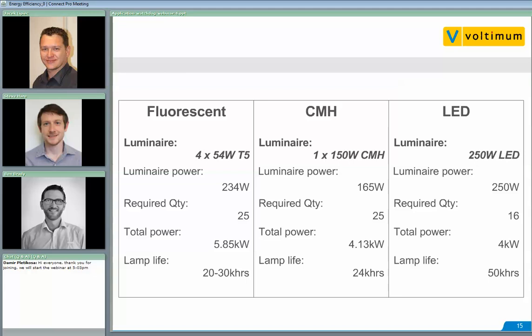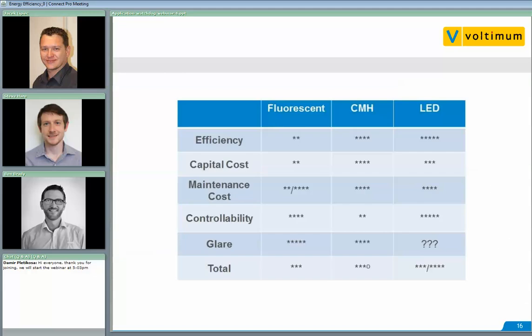Total power is not the only thing to compare when looking at different light sources. Comparing across five areas — efficiency, capital cost, maintenance cost, controllability, and glare — using a star system where five stars is very good and one star is very bad: for efficiency, LED got five stars, ceramic metal halide four stars, and fluorescent two stars being about 30% down. For capital cost, ceramic metal halide is generally cheaper — roughly speaking, fluorescent is twice the price unit per unit, and LED roughly three times that of CMH. However, LED uses fewer fittings, so it works out cheaper than fluorescent.